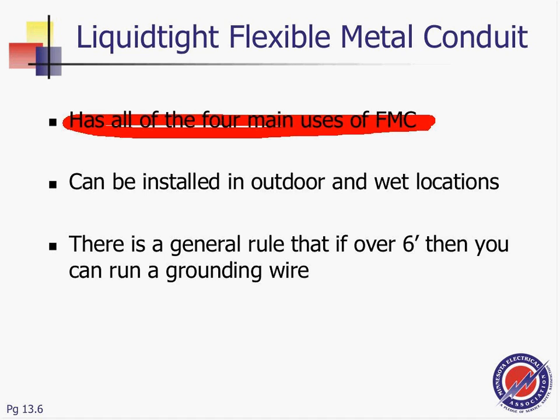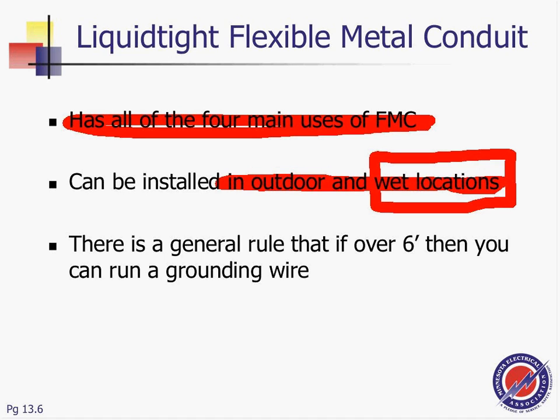Then, my friend, if you can use a flex, it would be a waste of money to use Liquidtight because it's more expensive, obviously, with the cover that they have. It can be installed in outdoor and wet locations. Really, this is the key point: it's wet location. If I have to summarize, the reason they have this is for wet locations. We know that if 6 feet or less, grounding, we're going to talk about grounding in a second. So this is only if flexibility is not an issue. If flexibility is an issue, then even though 6 feet or less, you have to ground.